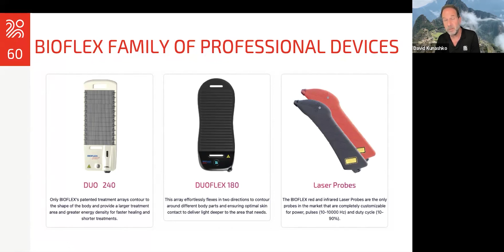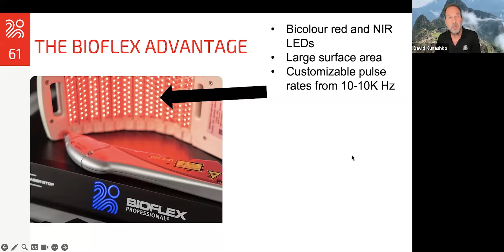So a little bit about these devices. The large surface array that we call the DUO array emits both red and near infrared light. It has a very large surface area of about 100 square centimeters. They're customizable, so you can change the pulse rate from 10 hertz to 10,000 hertz. You can change the power and the duty cycle in milliwatts. The diodes protrude out and touch the skin and push into the tissue, allowing for better absorption of light and less reflection.